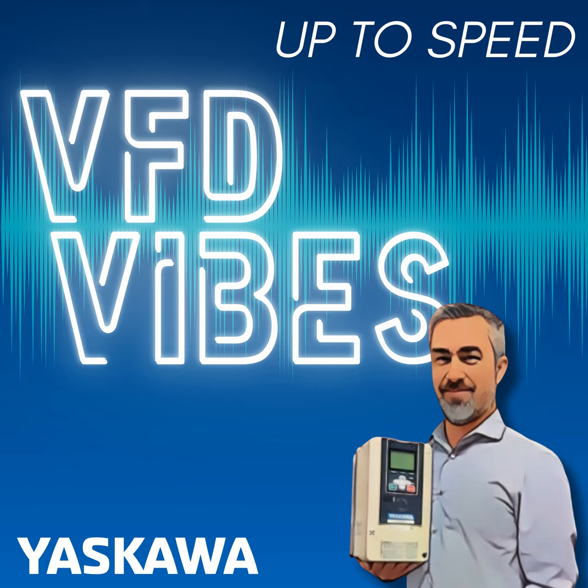One thing people will also say is if you have to get close to or cross high power lines, do it at a 90-degree angle. It has to do with the way electrical fields are generated and the noise that can get into the cable. In an industrial environment, I highly recommend the use of a shielded cable. We were just talking about the high voltage and its proximity - you definitely want to consider using that, because without it you can have just the introduction of more noise into it.